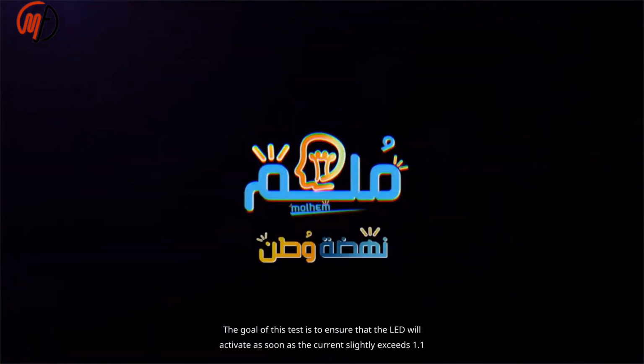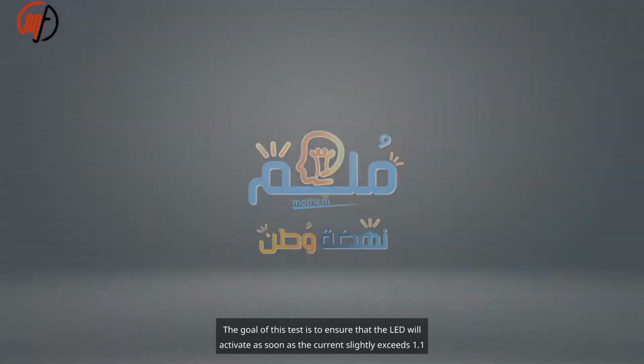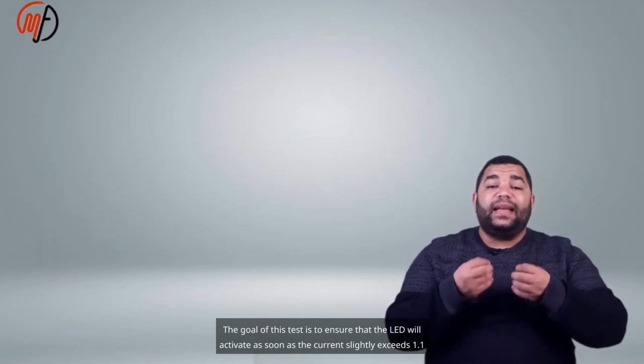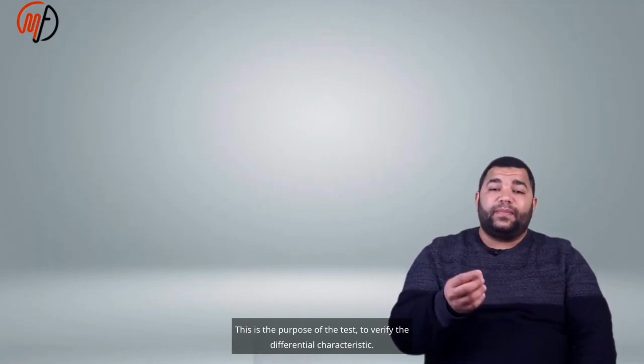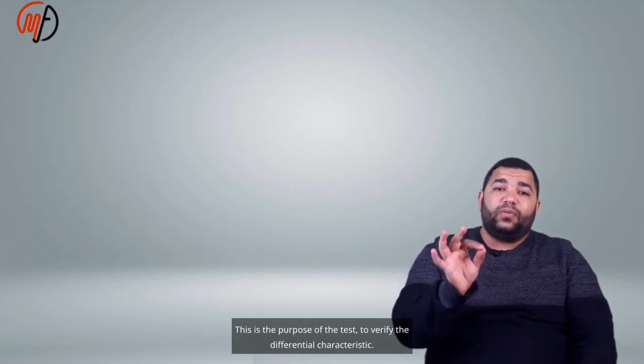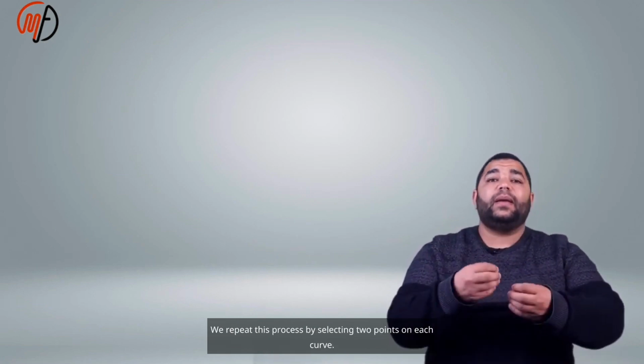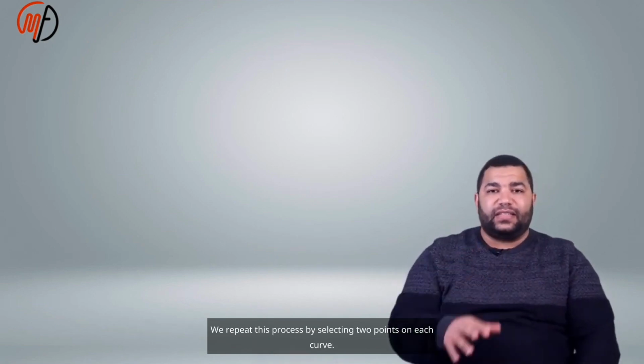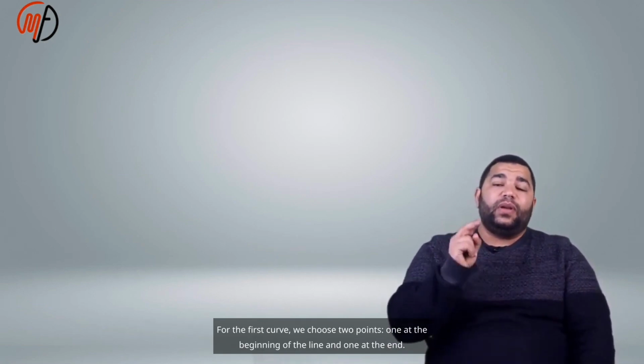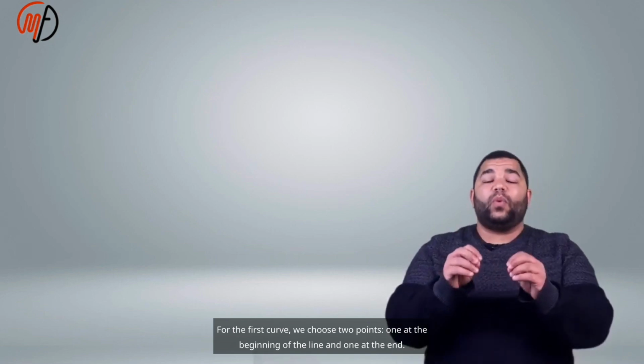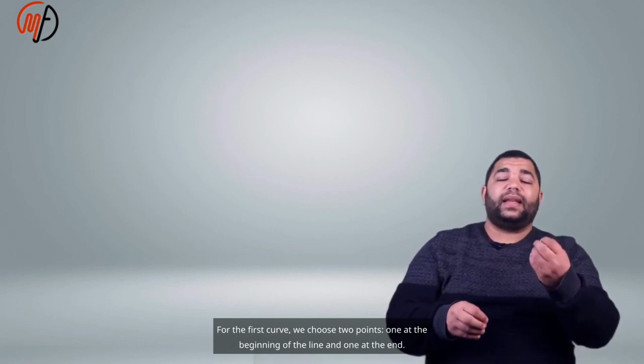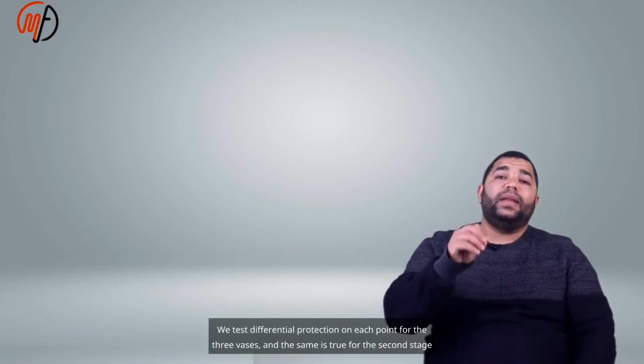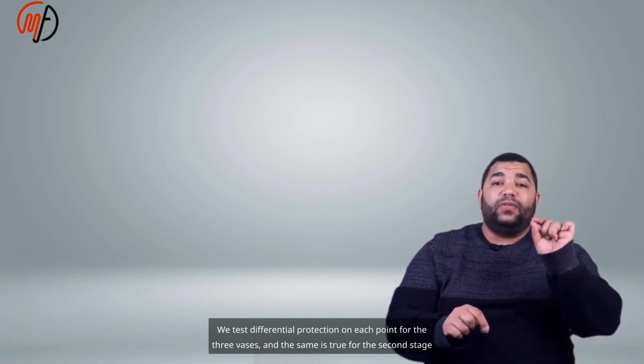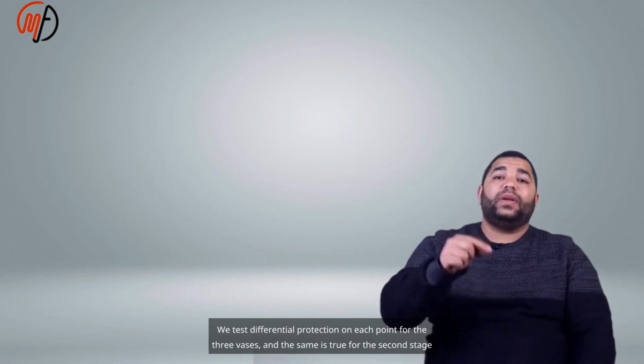The goal of this test is to ensure that the LED will activate as soon as the current slightly exceeds 1.1 amperes. This is the purpose of the test, to verify the differential characteristic. We repeat this process by selecting 2 points on each curve. For the first curve, we choose 2 points, one at the beginning of the line and one at the end. We test differential protection on each point for the 3 phases, and the same is true for the second stage.